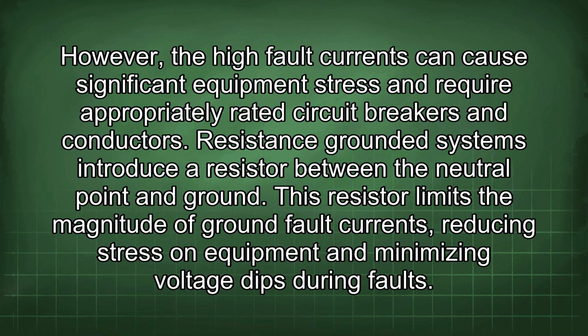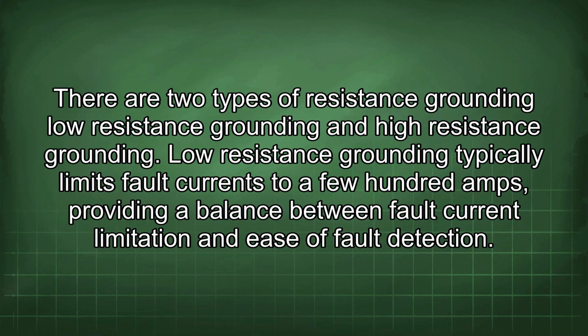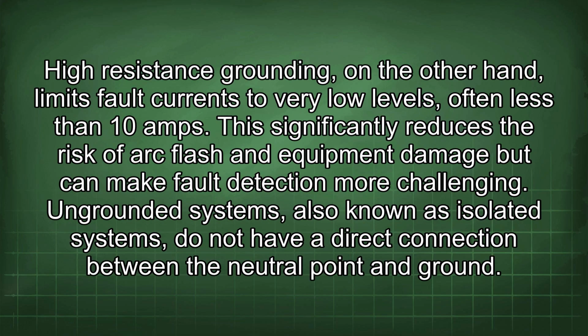Resistance-grounded systems introduce a resistor between the neutral point and ground. This resistor limits the magnitude of ground fault currents, reducing stress on equipment and minimizing voltage dips during faults. There are two types of resistance grounding: low resistance grounding and high resistance grounding. Low resistance grounding typically limits fault currents to a few hundred amps, providing a balance between fault current limitation and ease of fault detection. High resistance grounding, on the other hand, limits fault currents to very low levels, often less than 10 amps. This significantly reduces the risk of arc flash and equipment damage but can make fault detection more challenging.